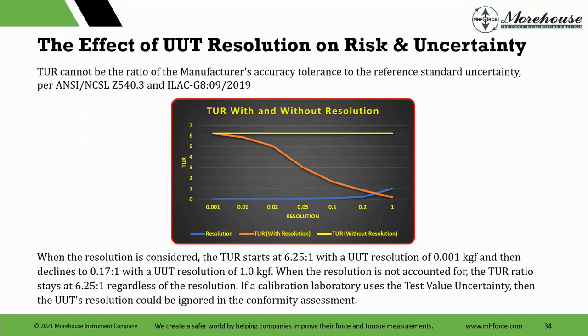So you can see the graph here, and you have TUR with and without resolution, right? Without, if I just do a simple calculation, a TUR, I could use a test accuracy too. I could use all kinds of stuff. And if I don't put the right stuff in the denominator, it's just going to stay the same. But if I put repeatability in the denominator, I put other error sources in, and then I put resolution in, it's going to change, right? And this graph shows what happens. As the resolution of a device increases, the test uncertainty ratio decreases. And then this came from a paper that Scott Mims wrote with this example.